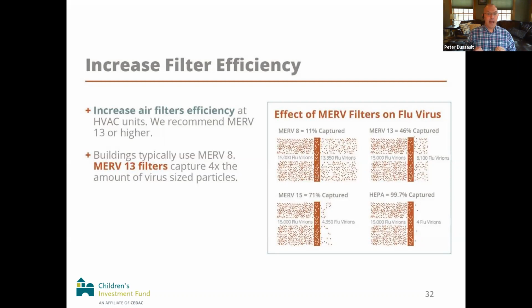The CDC and ASHRAE have said that instead of using a MERV 8 filter, use a MERV 13. If you use a MERV 13 filter, instead of only capturing 11% of virus-sized particles, you'll now capture 46%—a 4 times increase in the amount of particles removed from the airstream. You can go higher, to MERV 15 and above.